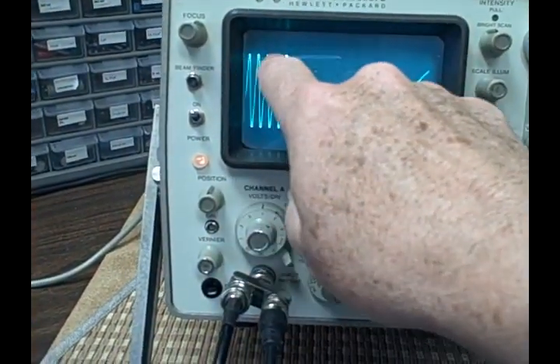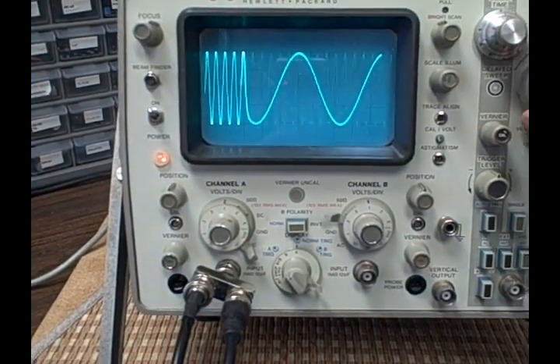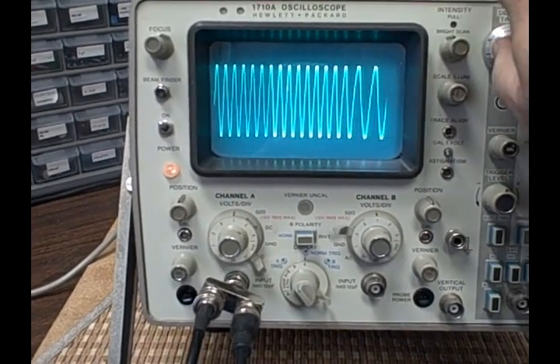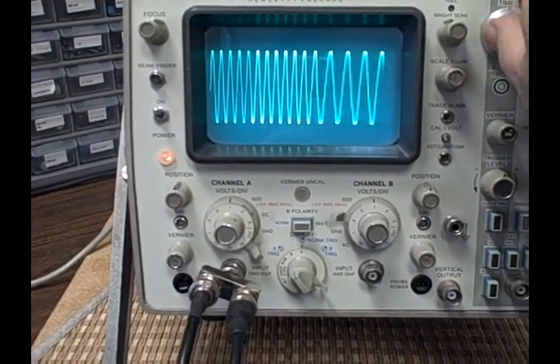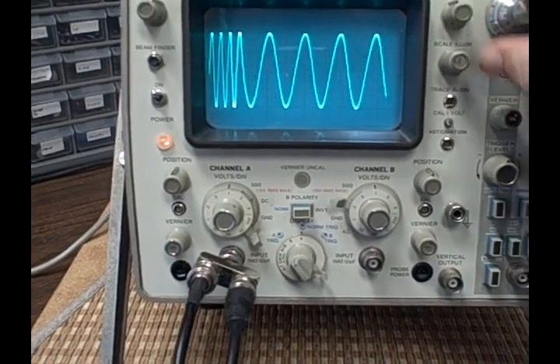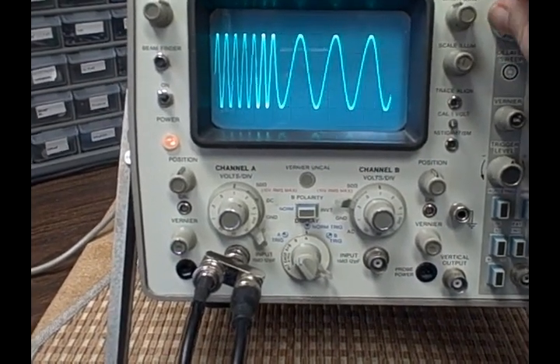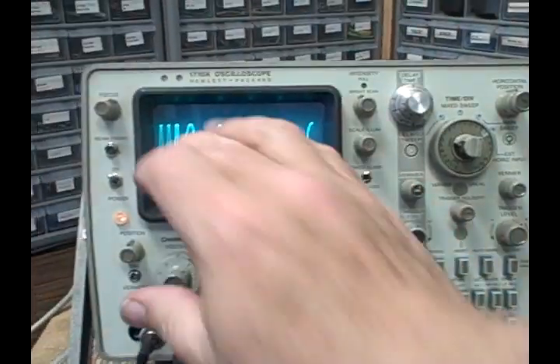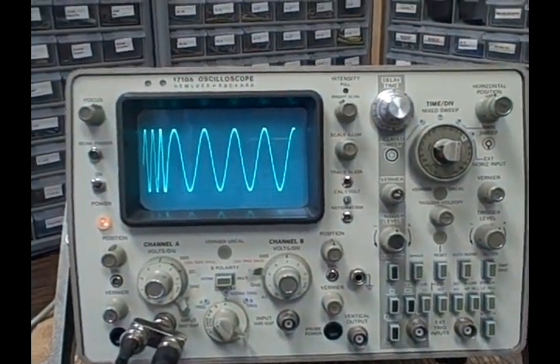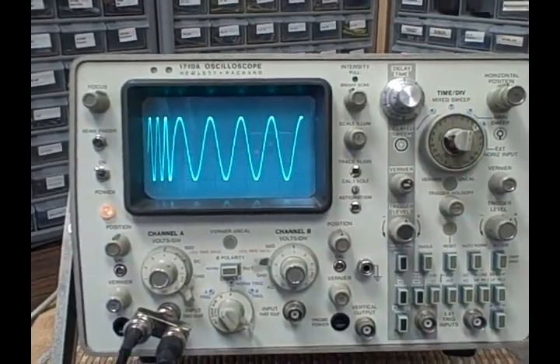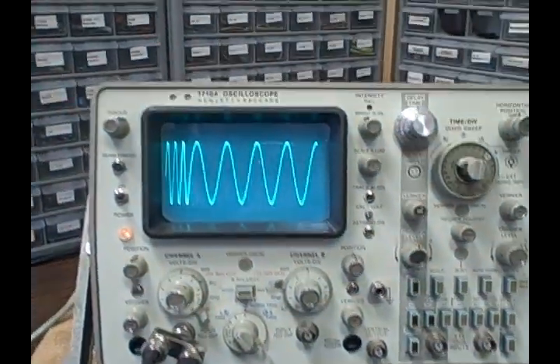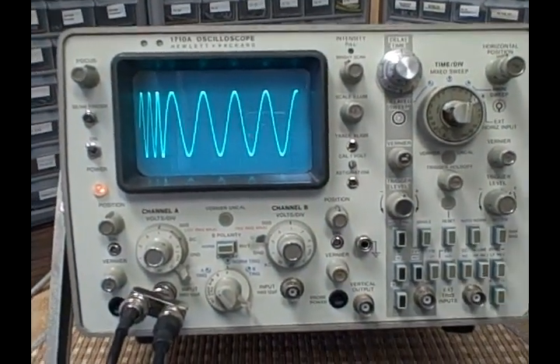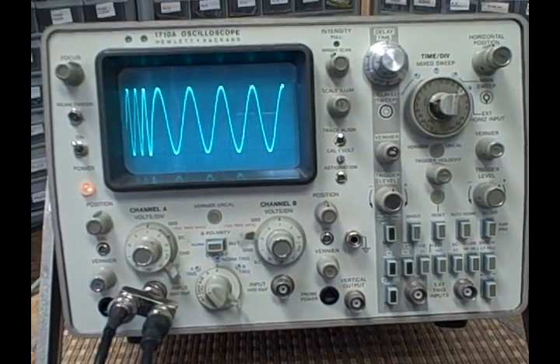You see that one, two, three, four, the original four are left alone, and I can rotate through the waveform looking at different sections of it as I care to. That's the idea of the delayed sweep. There might be something interesting on a complex waveform where you'd like to zoom in and take a look at that little area without having to change all of the settings and mess up what you were looking at. So you can do it this way.